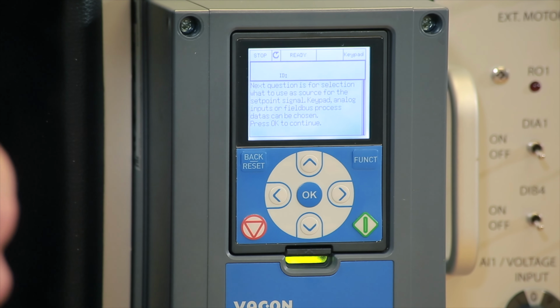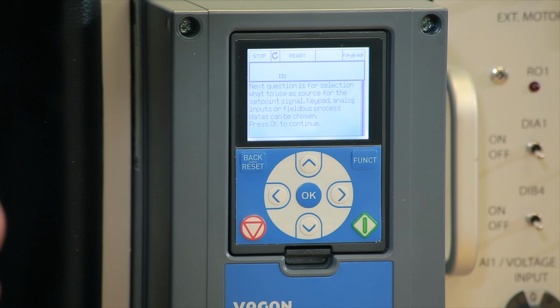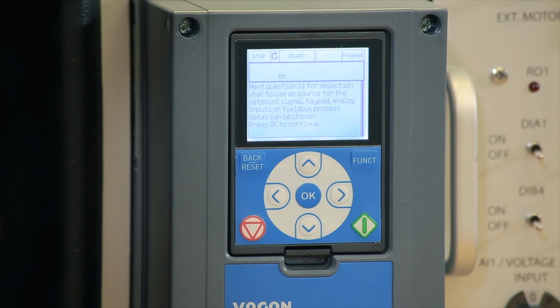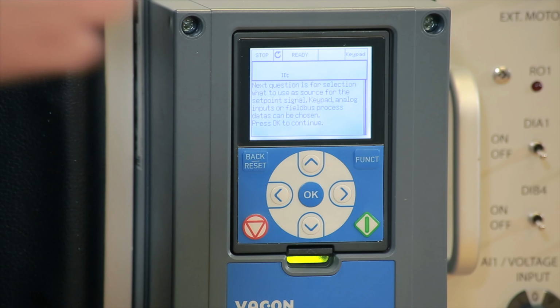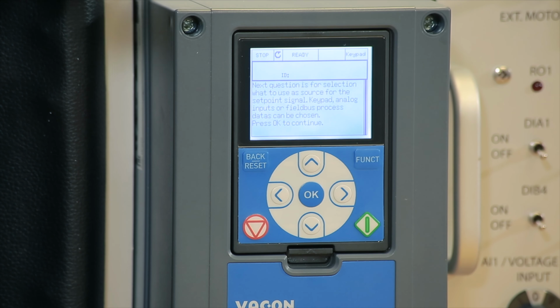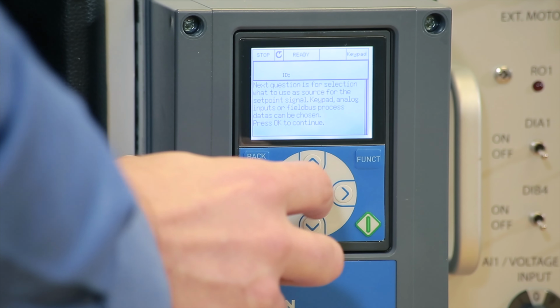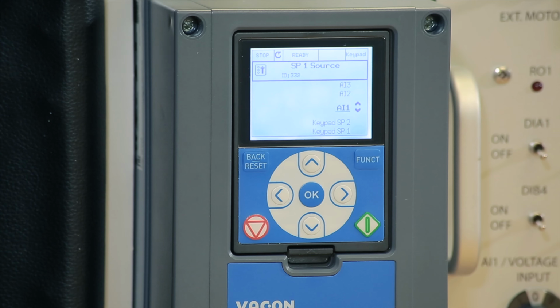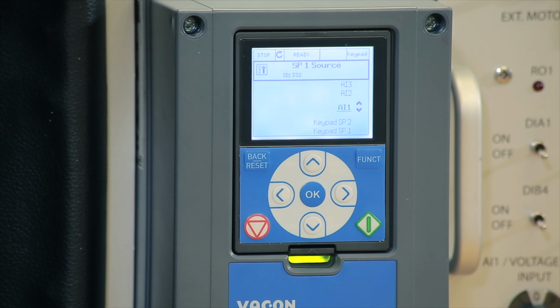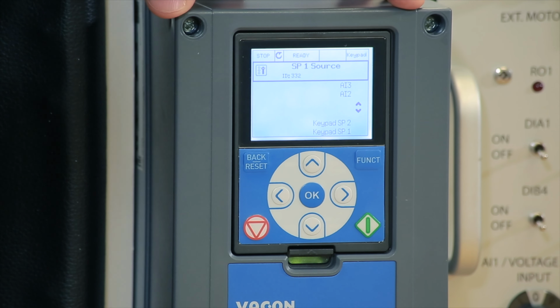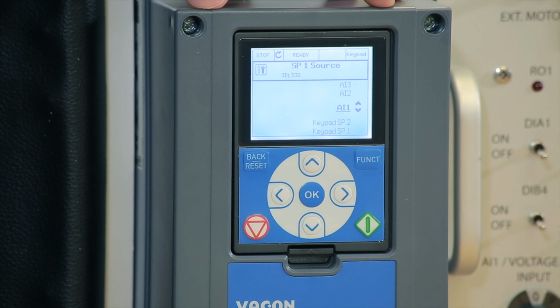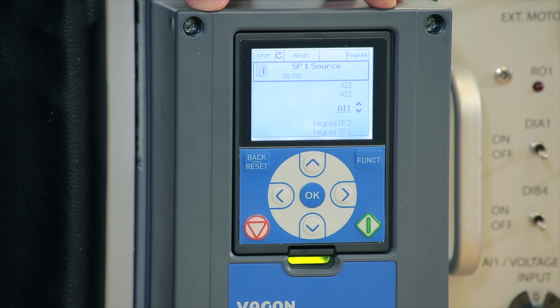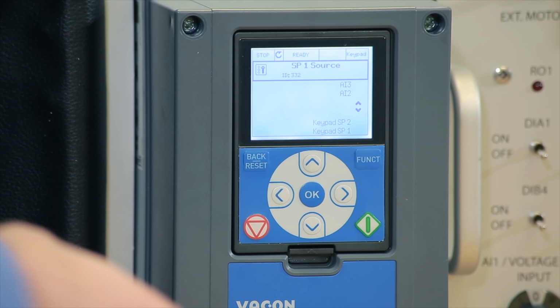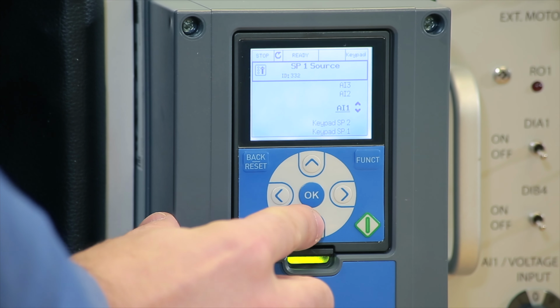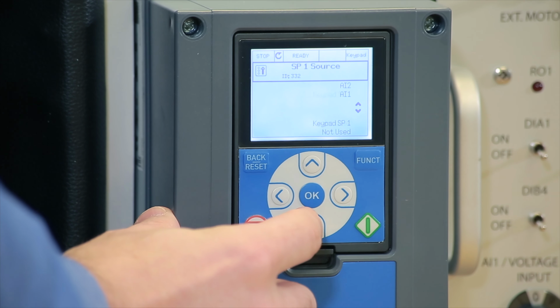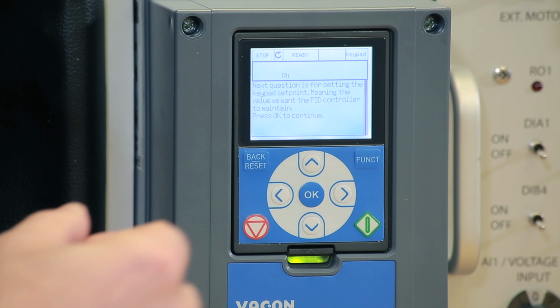Next, the drive asks for the selection of what to use as the source for the set point signal: keypad, analog inputs, or field bus process. So this basically says, where do we want to program the actual set point from? Because we have one drive and one pressure transducer, we want to use the keypad as the source for the set point for this pressure transducer. So we're going to scroll down with these arrows until we get to keypad set point 1. And then we select this.